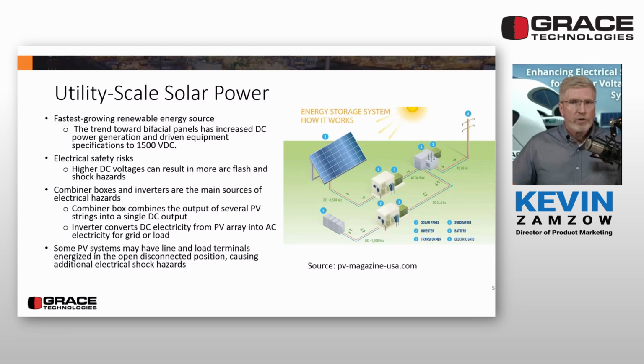The image is of a solar power generation plant with on-site battery storage. It does not show the solar array detail, which includes combiner boxes that aggregate energy from individual solar panels and can result in up to 1,500 volts DC on the load side that feeds into the DC to AC inverters. Maintenance of combiner boxes and inverters is a main source of electrical hazard. Without a through panel means to perform absence of voltage testing, electrical safety program procedures, including wearing proper personal protective equipment, must be followed.